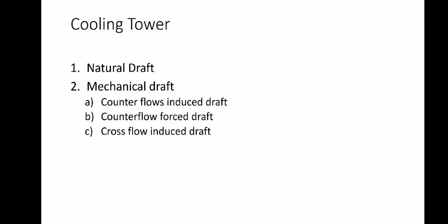The second one, mechanical draft towers, utilize large fans to force or suck air through circulated water. The water falls downwards over fill surface, which helps increase the contact time between the water and the air. This helps maximize heat transfer between the two. Cooling rates of mechanical draft towers depend upon their fan diameter and speed of operation.